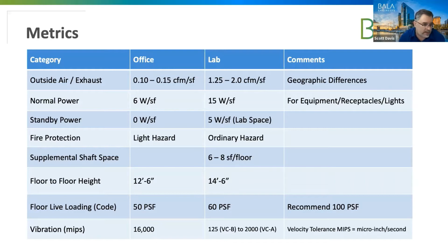And then Steve, if you wouldn't mind commenting on the structural elements here at the bottom. Yeah, so for an office space, the code minimum live load requirement is 50 pounds a square foot. However, what we've experienced, half the actual office buildings out there are designed to 100 pounds a square foot, and the other half are really down to this code minimum, 50 pounds a square foot. And then when you're moving over to lab, the code minimum again is 60 pounds a square foot, which is a small difference. But if you're doing a new lab today, you're going to really want to do it for 100, maybe even 125 pounds a square foot of floor capacity, just to catch any heavy localized equipment that's going in the space.